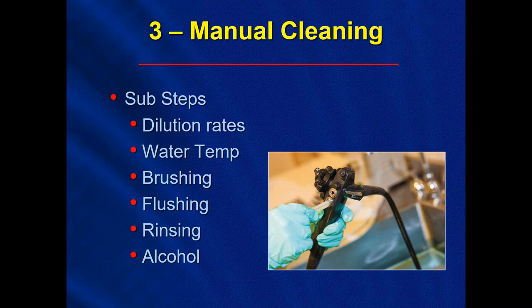In this one critical step, as we said, there's a variety of parameters that must be adhered to, such as proper dilution rates of your enzymatic solution to water, proper water temperature, effective brushing of lumens. You have to really be cognizant of all the steps involved and you need to adhere and follow these, including flushing channels, rinsing, and an alcohol flush to disperse water. Follow the manufacturer's IFUs for their particular scope and what is recommended.